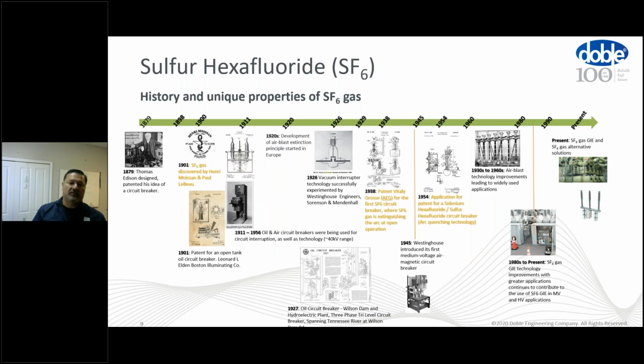So I love this slide because it kind of represents a number of things that happened throughout our industry. Obviously, with the invention and the patent of Thomas Edison's circuit breaker, at that point SF6 wasn't even discovered yet. It wasn't until 1901 when SF6 was discovered by two chemists, Henri Moissan and Paul Lebeau. But SF6 really did not come into play in breakers or GIE until much later. By like 1938, AEG first put out a patent where SF6 was being used as an actual arc quencher. Before that, it was vacuum interruption, obviously air and oil blast circuit breakers. So really interesting. But even still, it had a kind of a slow start.